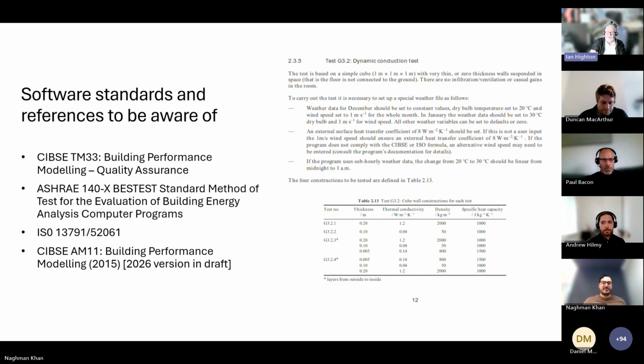I don't know if he's still going, but he had experience with. They had an internal tool called Room, and you had all four of us, like I said, IES, ESP, E+ represented by Design Builder and ourselves. All four vendors sat round, thrashed through these tests and managed to get within 0.6 of a degree and just a few percentage points in terms of energy consumptions and other values. So, you know, it's impressive. You got four totally independently developed engines giving you very, very similar results once we all sat around and agreed it.